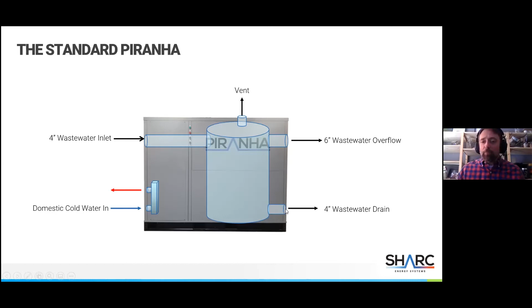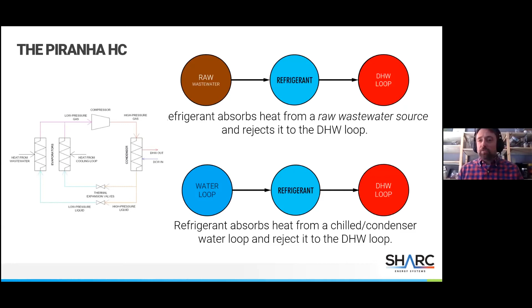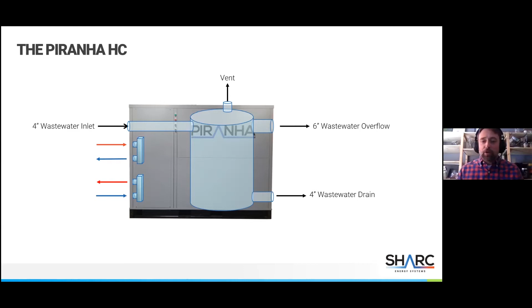The PIRANHA HC model, which I mentioned does heating and cooling, is very, very similar in process. So the heating process from the wastewater is the same, except what we've done is we've combined the process of taking heat from a condenser or chilled water loop and also then amplified the performance of the PIRANHA. So we're taking heat from raw wastewater as well as providing a chilled water source for building ambient cooling, things like that, to amplify and get that increased COP performance of the heat pump itself. Looking at that model, there really is no change in most of the piping. Fundamentally, we've just added that additional evaporator coil that's allowing us to provide chilled water out to a system.